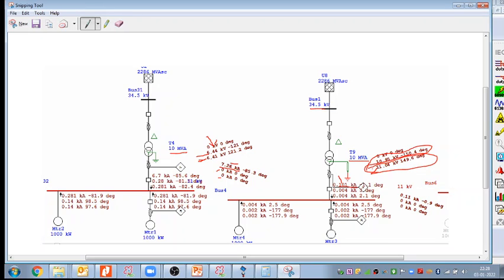voltage jumps to the line voltage. So what will happen is that when the voltage jumps to the line voltage, all the phase insulation we have to design for the 11 kilovolt. All the equipment rating, all the LA rating, surge resistor rating, all the equipment rating and insulation requirement will increase, and then the cost of the overall system will increase. Just to limit this current, I am increasing the overall system cost, right?